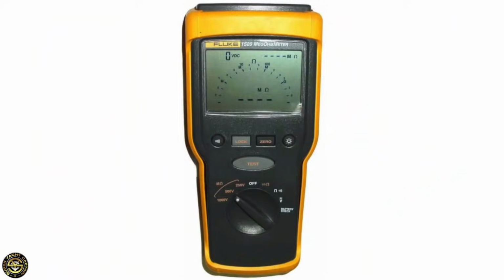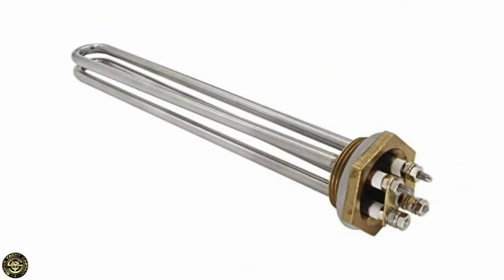So it says the continuity recorded a resistance in excess of 100,000 ohms. This is after the arcing. Going back to the report, the investigators used a digital megohmmeter to run a 500 volt DC insulation resistance test. So basically they put 500 volts DC from a megohmmeter through the heating element to test the insulation. And what they found is that on each element, the insulation had failed.